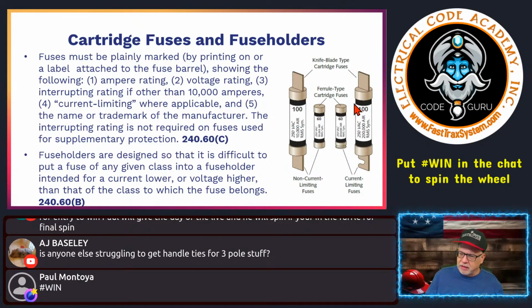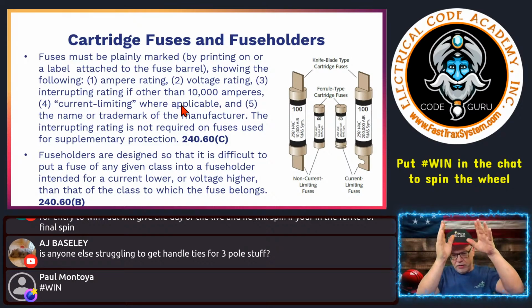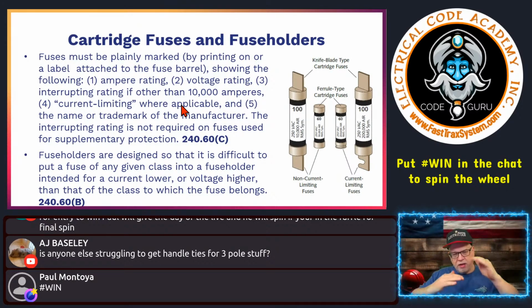Again, I still see these used a lot. There's a lot of fire pump applications, I think Brandon's working on fire pumps, that will still see fuse applications. A lot of times they're much easier to do selective coordination with fuses because of the ratings, and it's pretty easy. Whereas with a circuit breaker, you have to look at the signatures and the trip curves and overlapping and things like that. Sometimes it can be much easier with a fuse.